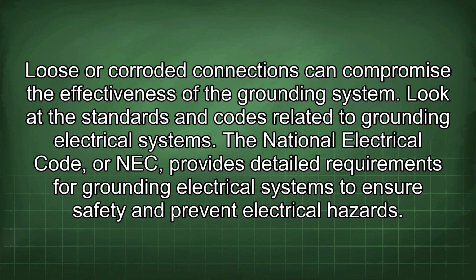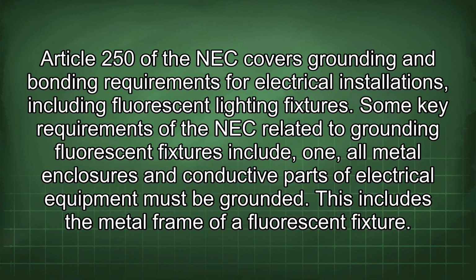The National Electrical Code, or NEC, provides detailed requirements for grounding electrical systems to ensure safety and prevent electrical hazards. Article 250 of the NEC covers grounding and bonding requirements for electrical installations, including fluorescent lighting fixtures. Some key requirements of the NEC related to grounding fluorescent fixtures include: 1. All metal enclosures and conductive parts of electrical equipment must be grounded. This includes the metal frame of a fluorescent fixture.